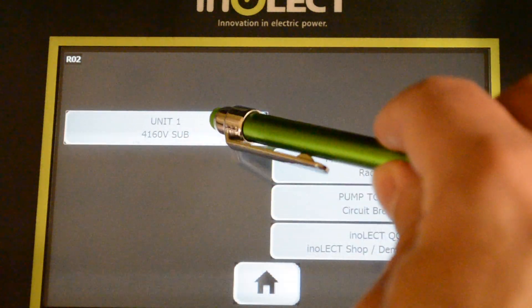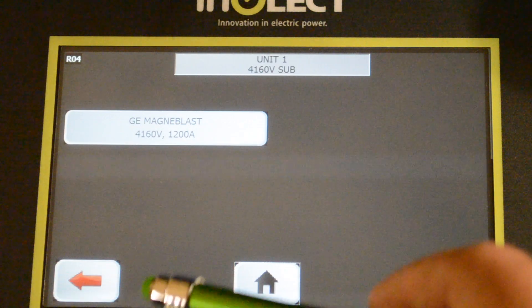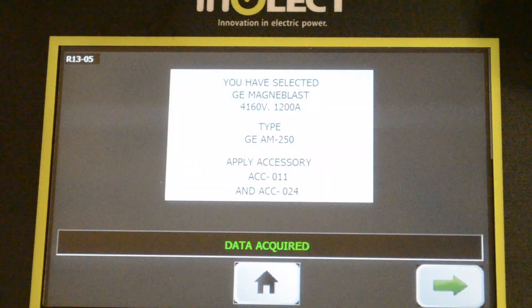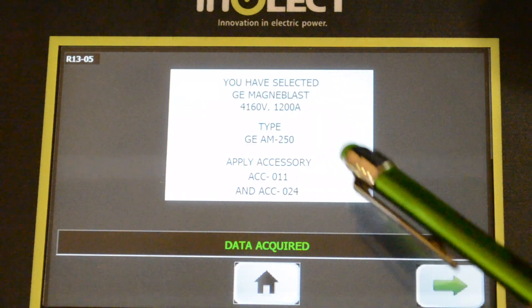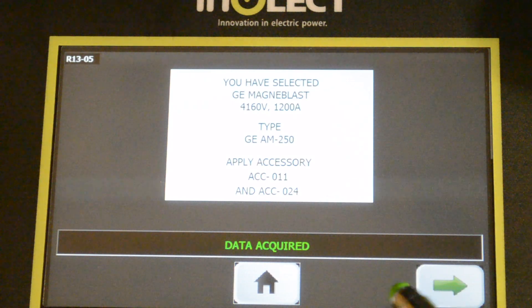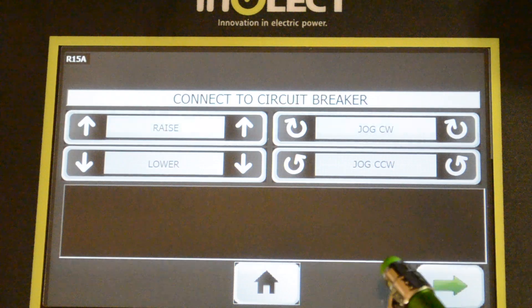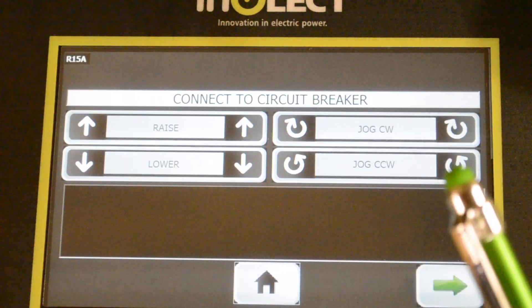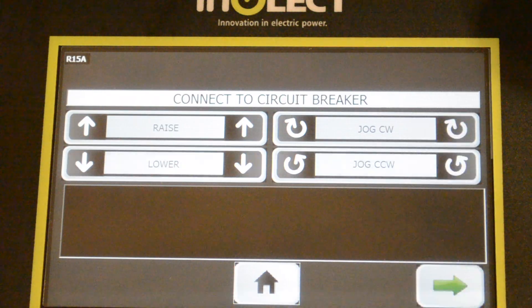For this particular demonstration we had one that said Unit 1, 4160 sub. You can have up to five buttons on each side of the screen, giving you ten parent buttons, and then up to ten child buttons or breaker profiles on the page. Once we access the GE Magne-Blast button, it gives us a confirmation screen: you've selected this type — this is a GE AM-250 MVA version — and the accessories are engraved with accessory numbers so you always know which accessories to grab and connect to the breaker. You can also use raise and lower here to adjust vertical height, and adjust the rotation of the motor if needed to connect.